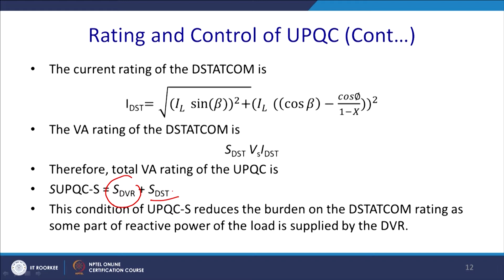This condition of the UPQC reduces the burden on the individual voltage source converters. What happened in the earlier UPQC-Q and UPQC-P is that one of the converters is burdened more. Here the load has been shared by both the converters equally. UPQC reduces the burden on the D-STATCOM rating, as some portion of the active power and some portion of the reactive power of the load is supplied by the DVR. So, let us see some reference generation techniques that are required to control the UPQC.